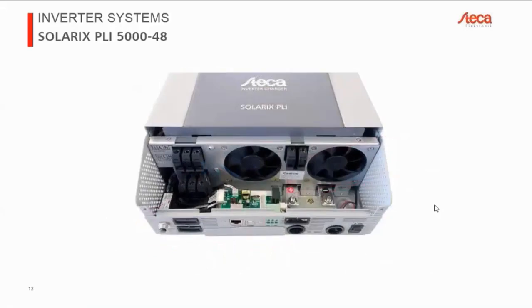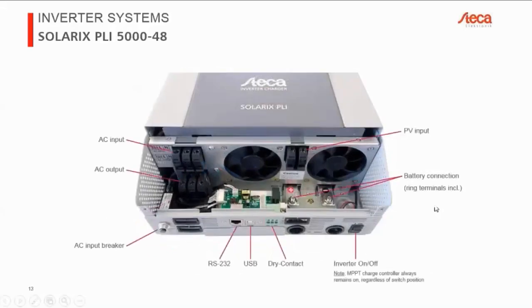This is the 5 kilowatt, 48 volt version, very similar. Again, we have an AC input, AC output. The AC input breaker is slightly larger now. It's designed for 40 amps, which is equivalent to about 9.2 kilowatts for a 230 volt system. So that's how much energy you can take from the AC input. That's the absolute maximum that you can pass through the device.